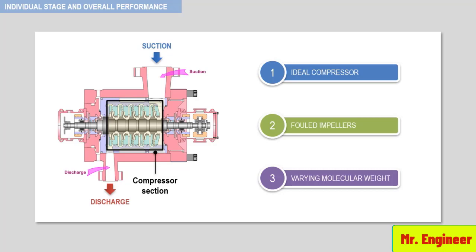best efficiency point. It is important to understand here that in many applications, operating at the compressor section rated point does not mean operating at each individual compressor impeller best efficiency.